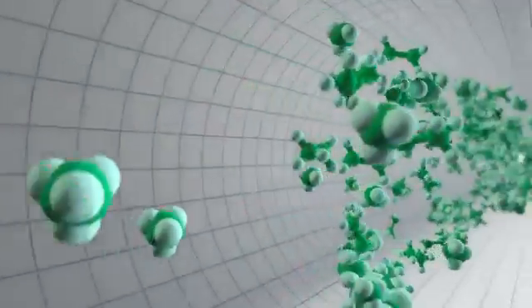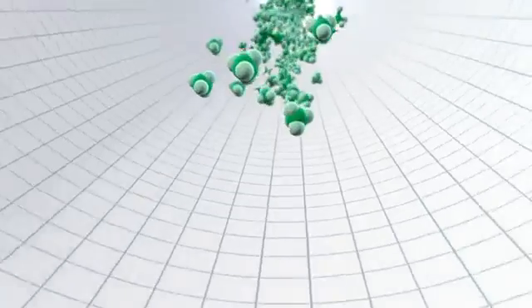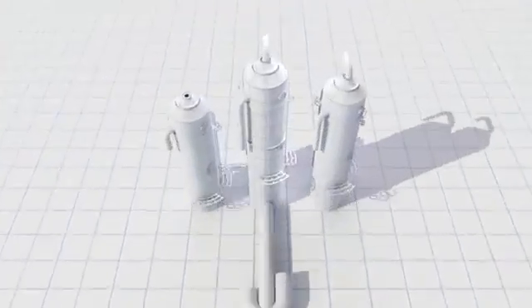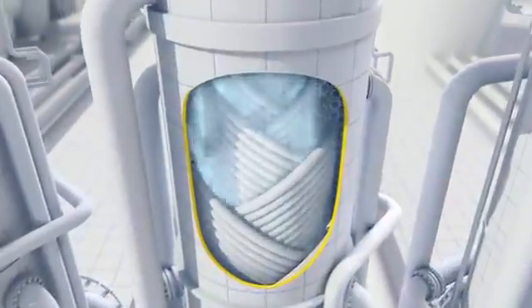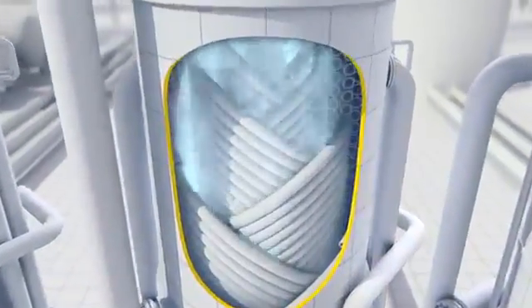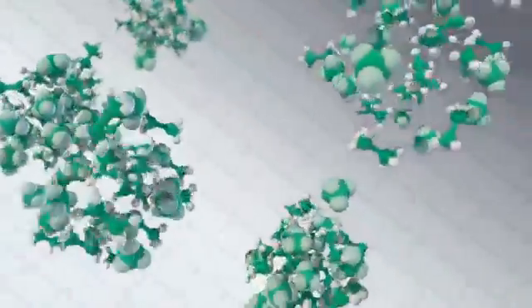Now the purified natural gas, methane with some ethane, is ready to be liquefied. This happens in heat exchangers. A coolant, chilled by giant refrigerators, absorbs the heat from the natural gas. It cools the gas to minus 162 degrees centigrade, shrinking its volume by 600 times.